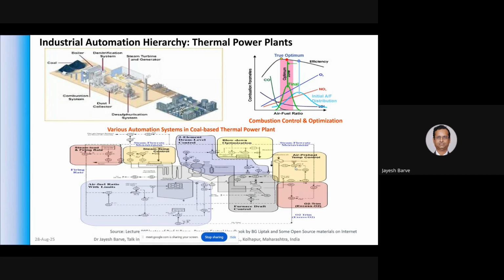You know the steam tables - higher the pressure, the steam boiling point will be higher, so temperature has to be higher. So temperature control and flow control of steam are coupled. All these things require control loops or automation systems around them. So all these automation loops or systems are actually working in tandem, collectively interacting with each other.